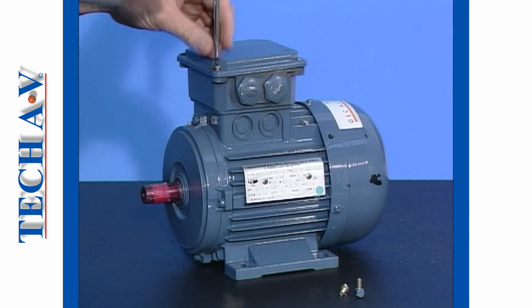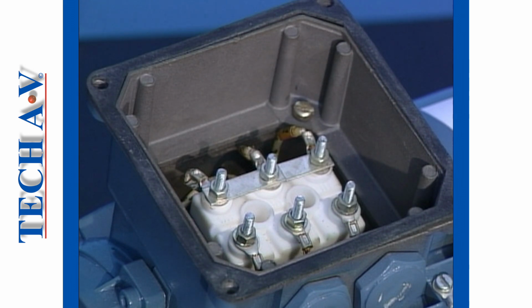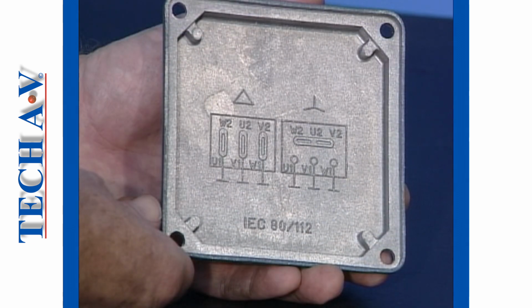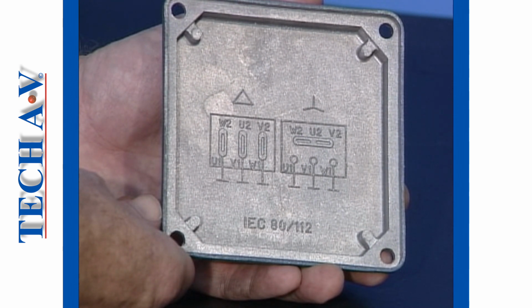Access to the stator windings is made in the motor's terminal box. Inside the box, we find that the ends of each winding are connected to a terminal block. A wiring diagram inside the lid of the box indicates the terminal post layout and where each winding is terminated.